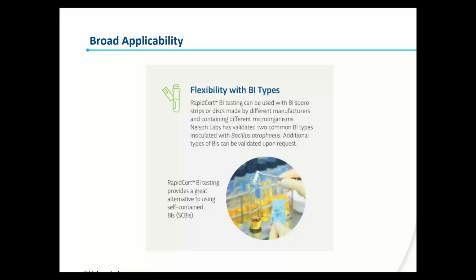And I did want to point out that the RapidCert BI test is a great alternative for the self-contained BI. Self-contained BIs do have a reduced, a shortened incubation time, but they can also be potentially prone to breakage that might be difficult to detect within that sterilization load. It can be tricky because an SCBI is not always well suited for the type of environment that it's used in. So this is an industrial environment, forklift, so there is a potential for breakage there. So this RapidCert test is a great alternative for those who are already utilizing SCBIs.